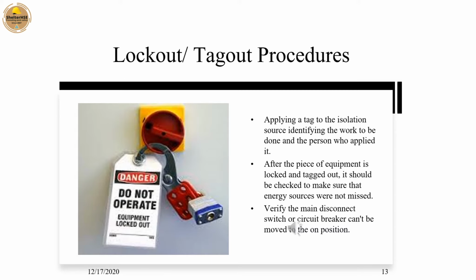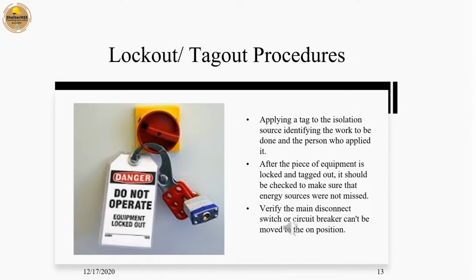After the piece of equipment is locked and tagged out, it should be checked to make sure that energy sources were not missed. Verify the main disconnect switch or circuit breaker can't be moved to the on position.